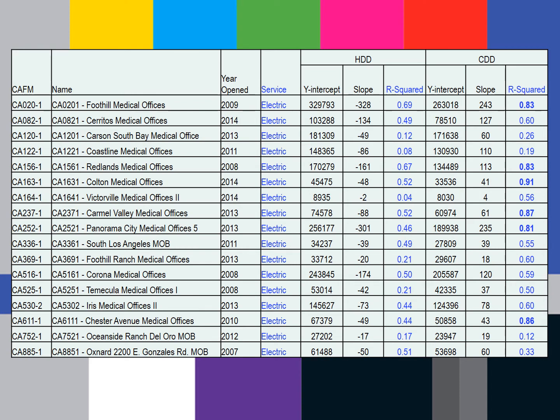And in most cases, that correlation is poor. For a good statistical model, you're looking for an R-squared value of 90% or better. I've highlighted anything that's better than 70% here. But even then, you can see that 3/4 of the time, the correlation between cooling degree days and electrical consumption is literally very bad.